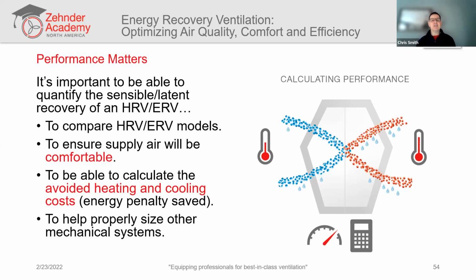Also, we want to be able to ensure that the supply air, this outdoor air that's coming into the building and being delivered to the living spaces, is going to be comfortable. So the performance of the HRV or ERV will impact that comfort. And we said this is a big reason why this matters. Also, we want to be able to calculate the avoided heating and cooling costs. So we know there's going to be an energy penalty to our ventilation. We want to eliminate as much of that energy penalty as we can. Well, how much of it can we eliminate? Calculating the performance will tell us. And then based on what we learn after we calculate the performance, that will help us properly size the heating and cooling equipment.